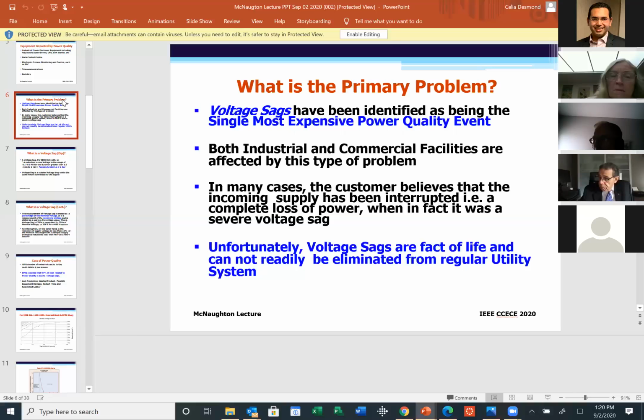Remember, each one of these sags potentially could cause a system upset if we did not have the proper, what we call mitigation equipment. The reason I have the last bullet point in blue is to emphasize that, unfortunately, voltage sags are a fact of life and cannot readily be eliminated from the regular utility. It has been here since the early 80s, and I'm going to show you later a slide that I captured just last month to show you a severe voltage disturbance. Next slide, please.